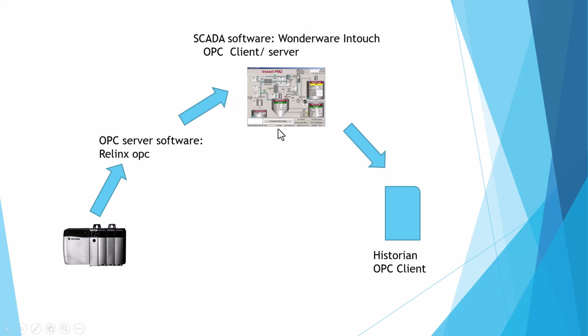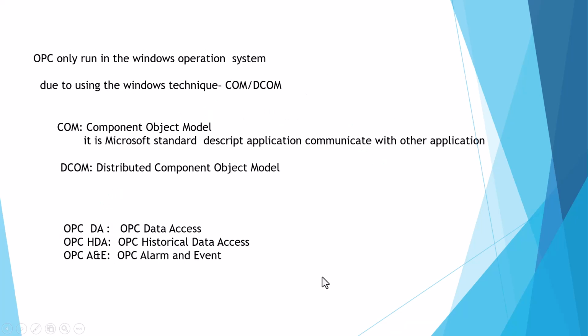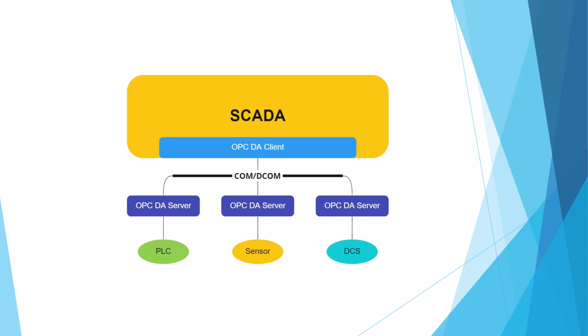In the SCADA, the display of real-time data is called OPC-DA, data access. If you want to display the trending of the system, you can call the historian database. That's called OPC HDA. If you want alarm and event activity, you can call OPC A and E in the OPC client. Here we show how SCADA OPC communicates with PLC, sensor, DCS. The PLC, sensor, DCS use OPC-DA servers, then use COM and DCOM, the Microsoft Windows technique, to communicate with the OPC-DA client.